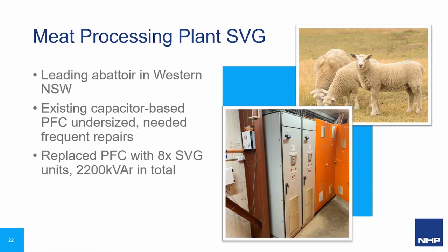were identified. Now, from that point, before we even went down a route of looking at repairs to even salvage what they had existing, as a baseline, we opted to conduct power quality audits throughout all the various main switchboard locations on their site. The reason being their load profiles have changed dramatically over the years. The plant's been in production and it's obviously expanded a lot since then. So those studies allowed us the clarity we needed to size exactly what systems they required and look at the existing cap-based systems and see if they were even feasible or adequate to cope with their current system.